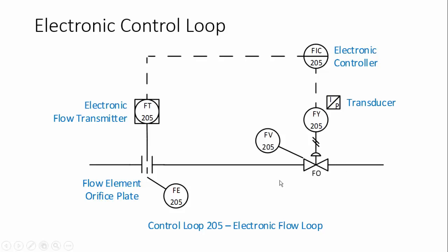There's a flow meter. It's an orifice plate. There's the flanges. It shows the orifice opening. There is an instrument on it, which is a discrete instrument mounted in the field, and it is a flow element, which is 205. So you can read these loop diagrams simply by understanding the symbols and the symbology that goes around making up these systems.